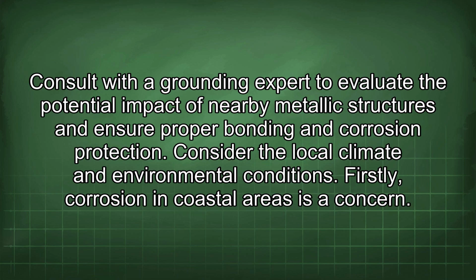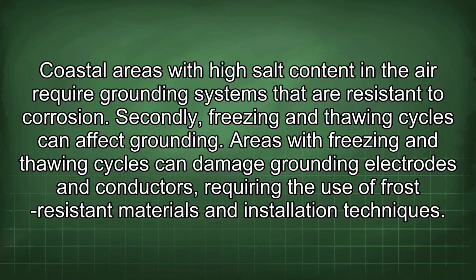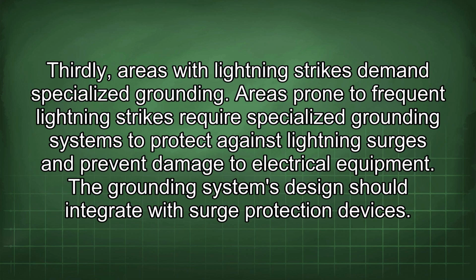Firstly, corrosion in coastal areas is a concern. Coastal areas with high salt content in the air require grounding systems that are resistant to corrosion. Secondly, freezing and thawing cycles can affect grounding. Areas with freezing and thawing cycles can damage grounding electrodes and conductors, requiring the use of frost-resistant materials and installation techniques. Thirdly, areas with lightning strikes demand specialized grounding.